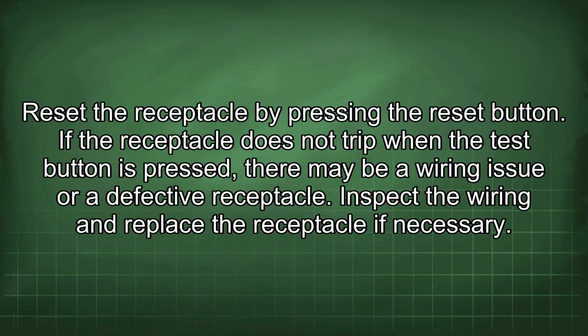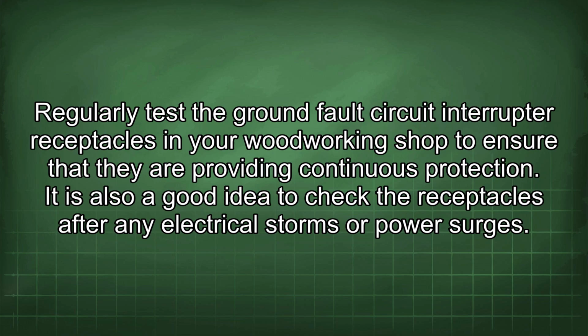If the receptacle does not trip when the test button is pressed, there may be a wiring issue or a defective receptacle. Inspect the wiring and replace the receptacle if necessary. Regularly test the ground fault circuit interrupter receptacles in your woodworking shop to ensure that they are providing continuous protection. It is also a good idea to check the receptacles after any electrical storms or power surges.